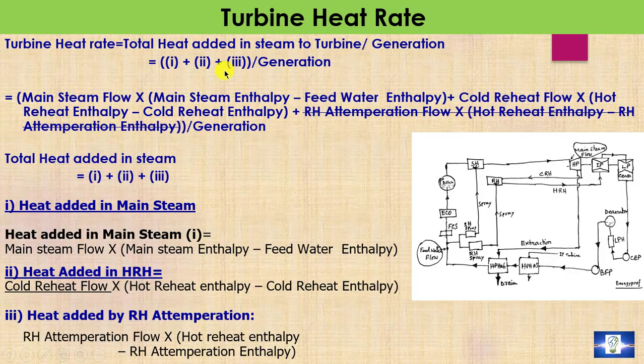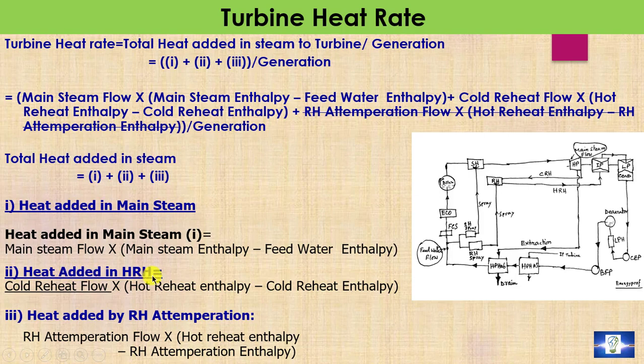The second question is the turbine heat rate. Turbine heat rate equals total heat added to steam in the turbine divided by generator output. The total heat added is divided into three parts: heat added in main steam, heat added in the reheat system, and heat added by reheater attemperation. In our case, reheater attemperation is zero. The heat added in main steam equals main steam flow × (H1 − feed water enthalpy). The heat added in the reheat system equals cold reheat steam flow × (H3 − H2).